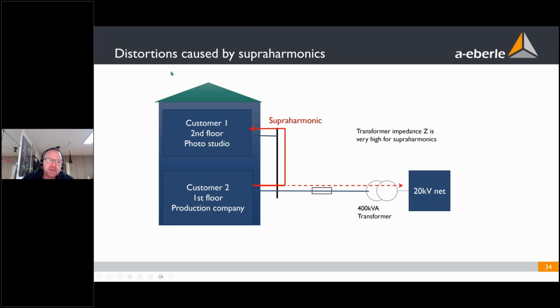So this was a building with a photo studio. The photo studio was on the upper floor of the building. The whole building was connected to the public grid with a 400 kVA transformer. On the first floor of this building, there was a big production factory, and they are using motors with frequency converters. And all the frequency converters produce some high frequencies with 8 and 16 kilohertz. And the 8 and 16 kilohertz on the current can be transferred with a transformer.